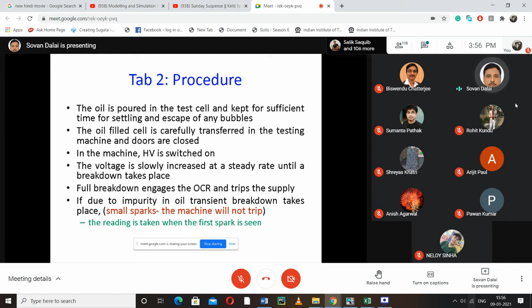This is the weak portion of the oil. When you get the transient breakdown, that reading is taken as one of the 6 readings. If the transformer oil contains more impurities, meaning it is more aged, then instead of the full breakdown voltage you may get all the breakdown voltages as transient in nature. For your general remembering, the number of breakdowns should be 6, whether they consist of complete, transient or final breakdown.